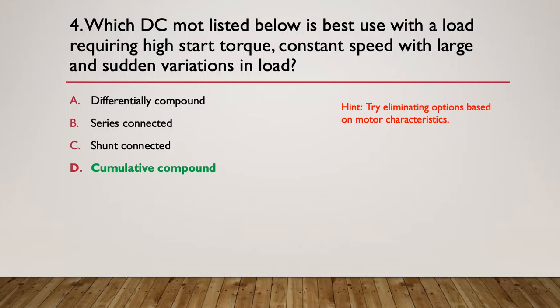The answer is the cumulative compound motor is going to give us the best characteristics. So it has both a series and a parallel component to the field, and because it's in what we call cumulative compound, it gives us that great characteristics of high start torque, constant speed, and it can cope with large and sudden variations and changes in load. So it's a complex machine, but it does the best for those attributes.